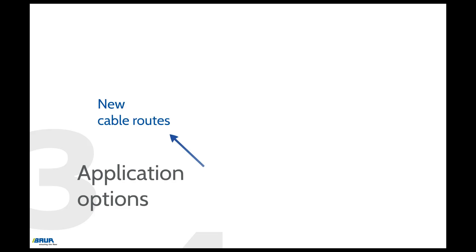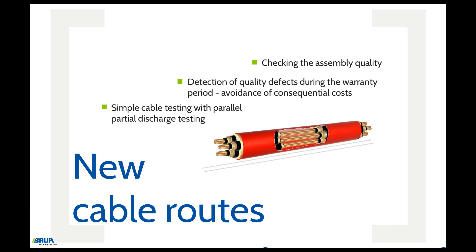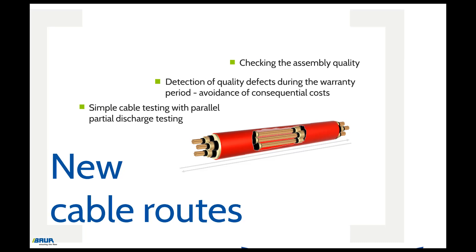Cable testing and diagnostics are used both on new cable routes before commissioning and on worn cables. Before the commissioning of new cable routes, testing and diagnostics are mainly used to check the assembly quality. Quality defects can be detected on time, thereby avoiding high consequential costs. In addition, newly laid cables are tested for safety-related defects by a simple cable test along with partial discharge testing.